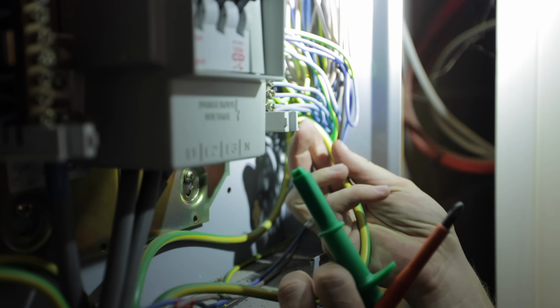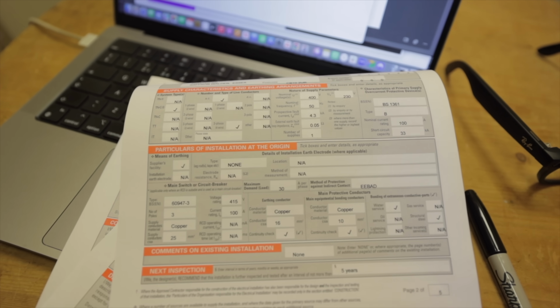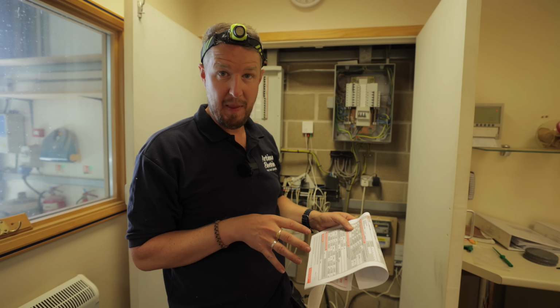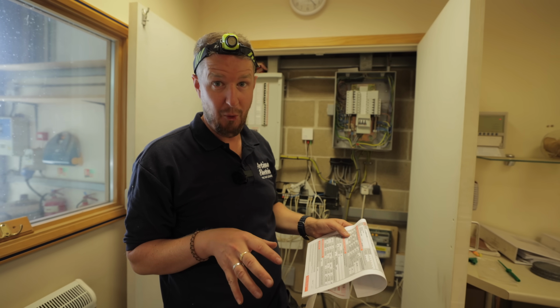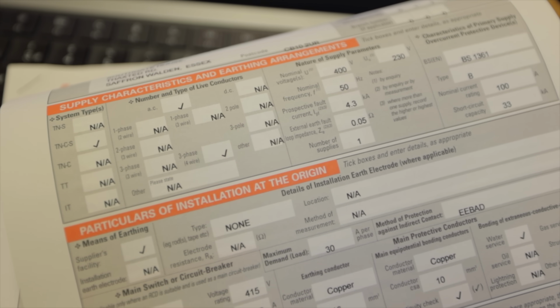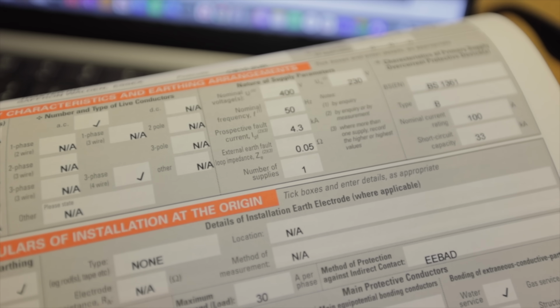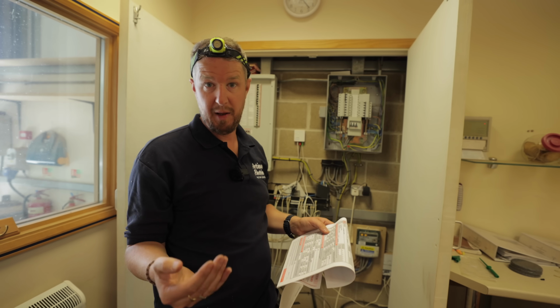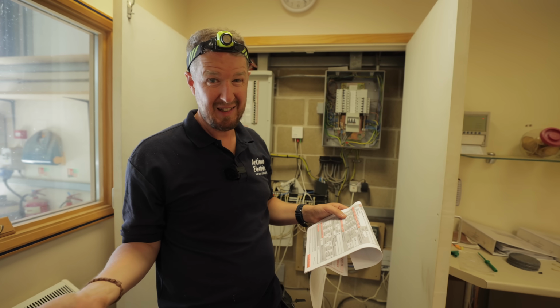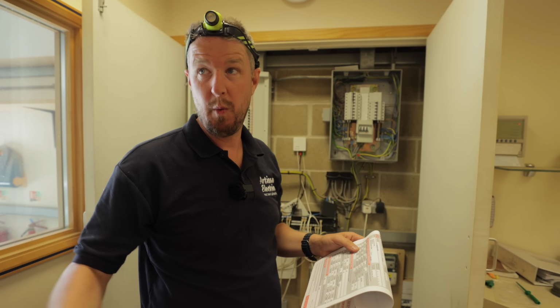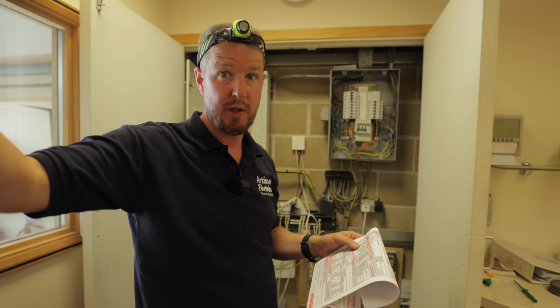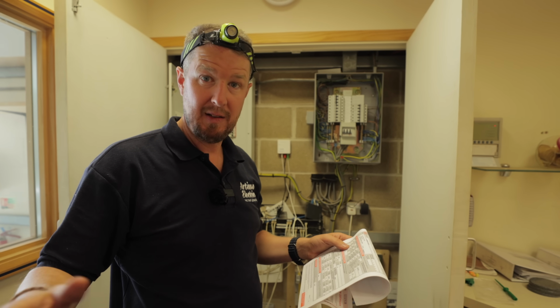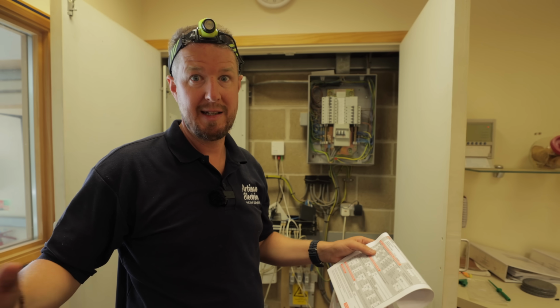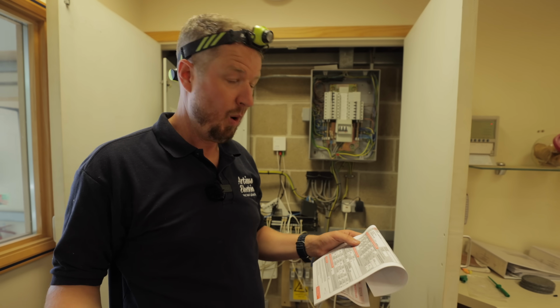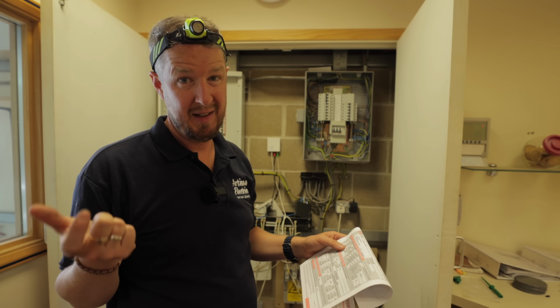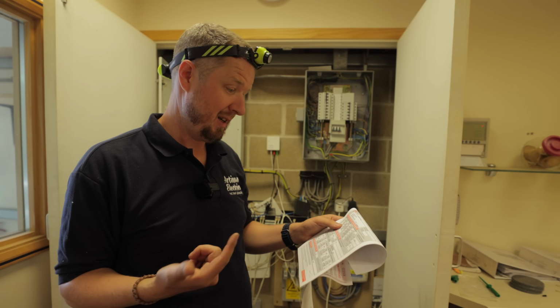Now, the interesting thing about this property is that we've got the original electrical installation certificate from when it was built in 2004, and we can see the original earth loop impedance reading, the ZE reading, was 0.05. It's actually gone up a little bit over time. I guess that's probably normal, but to be honest, I don't really know. We are really close to the transformer here, it's literally just behind the building. So it'd be interesting if you guys know anything about that, what kind of deterioration you might see over time, or if it's just the difference between test meters from when it was originally tested to now.